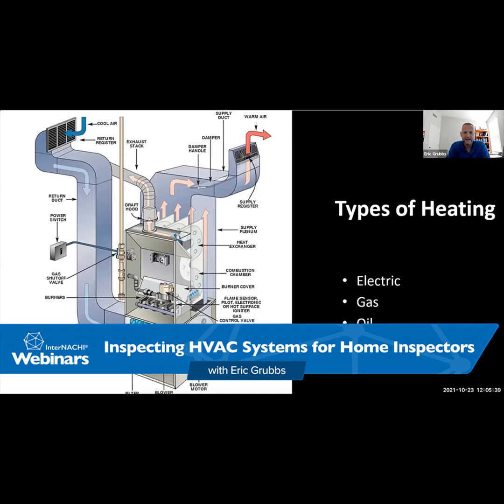You want rapid carryover flame. That means when it ignites, it's going to ignite each burner pretty quick and evenly. Should be a fairly quiet operation. It should be like a very low rumble, just nice, quiet. Like I said, if it's too high, then you've got some kind of combustion problems going on with that system, and it definitely needs to be addressed.